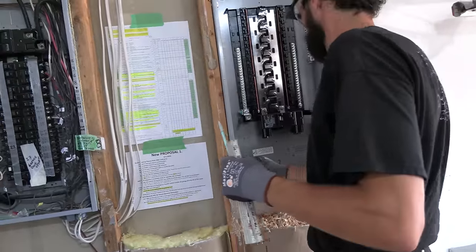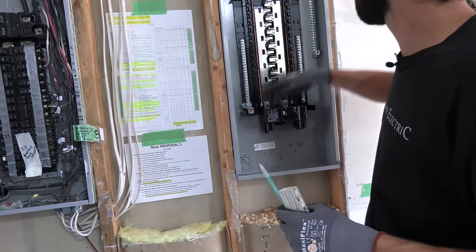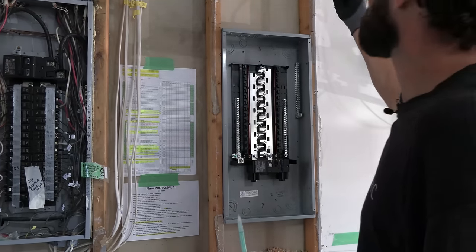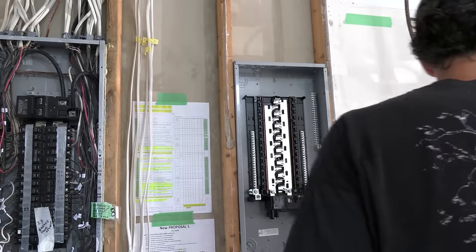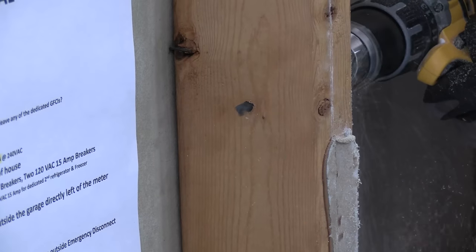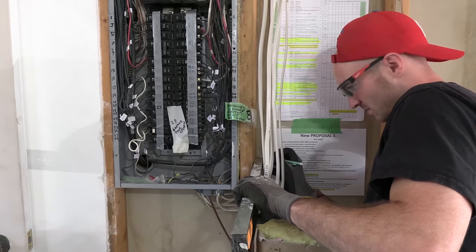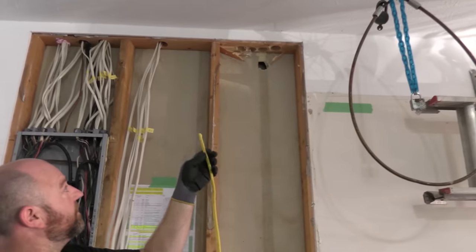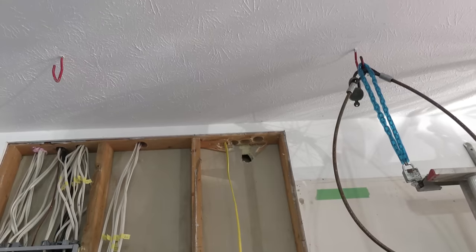We've got a flush fit back to the wall. A number of things we can do: drill that hole, knock this out, clean up loose debris, and install the nail plates at this point — they'll slide up underneath the drywall to protect anybody from penetrating that at a later date when mounting shelves. I've got two so if you can pop those off and slide a continuous one up there that'll be a better solution. I'm pulling wire on far distance — definitely helps to make the job easier, I keep one on my van at all times. Getting ready to feed this to Tim.